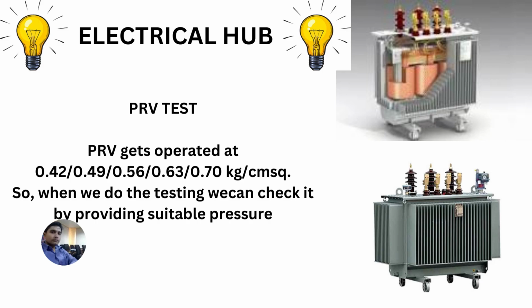So we can check it by lifting the pressure release valve with a certain pressure. If it gets lifted, it means that it is okay and we can complete our commissioning test.